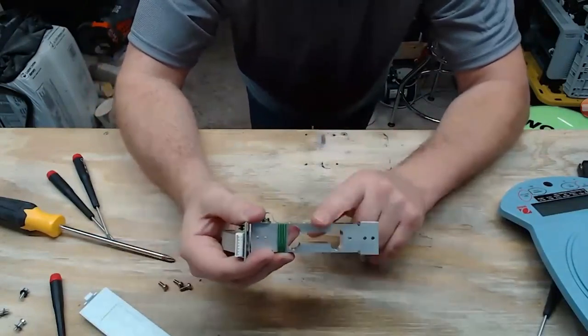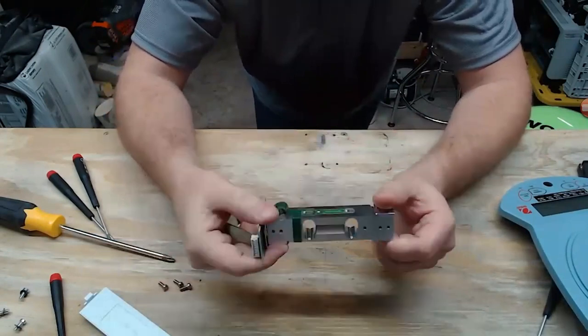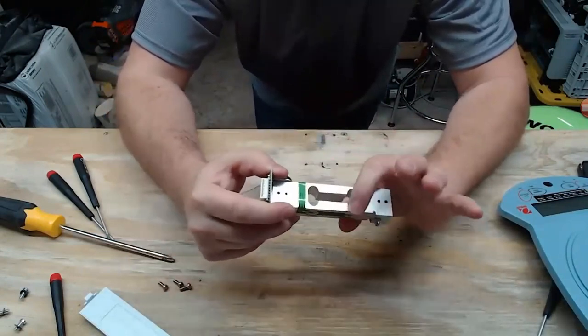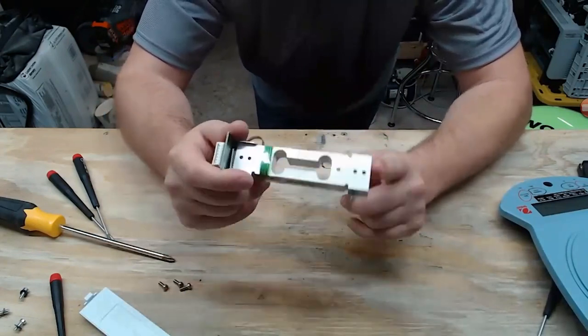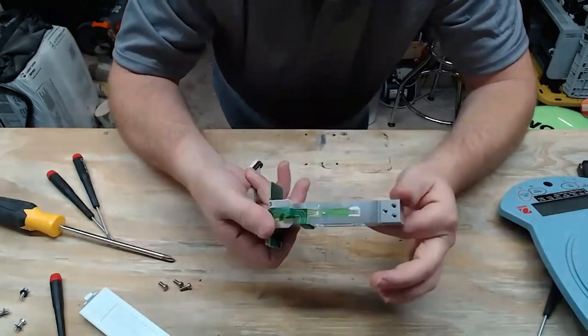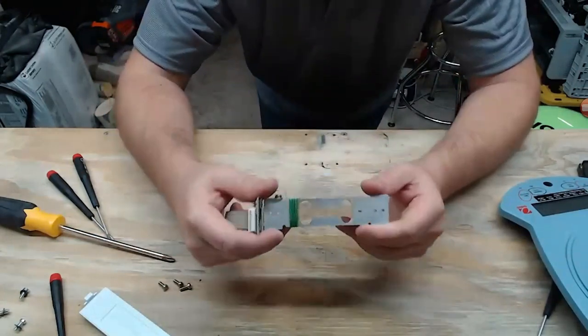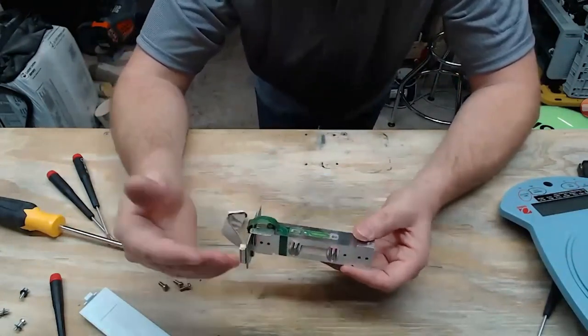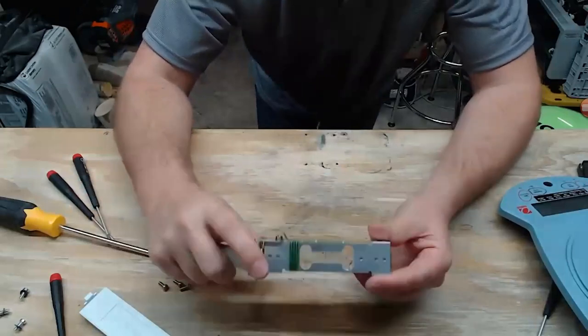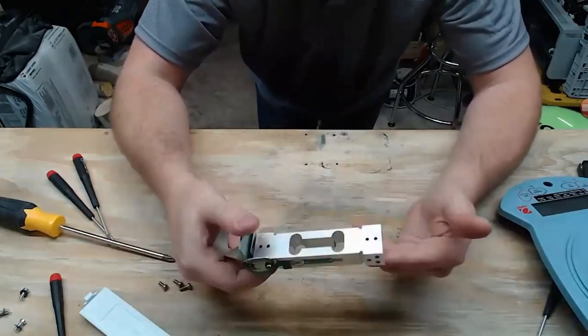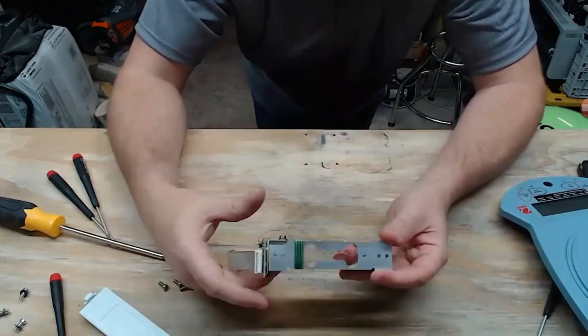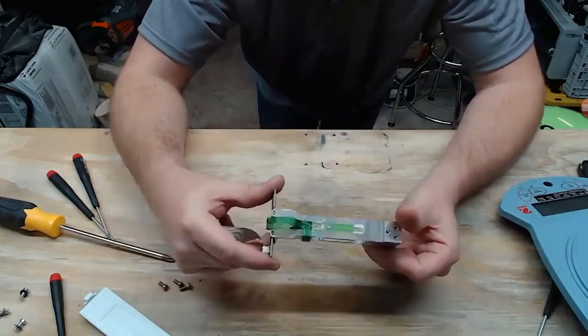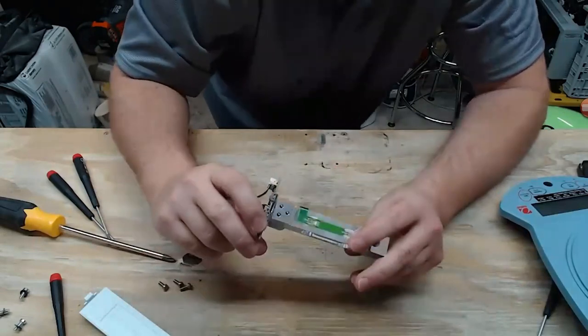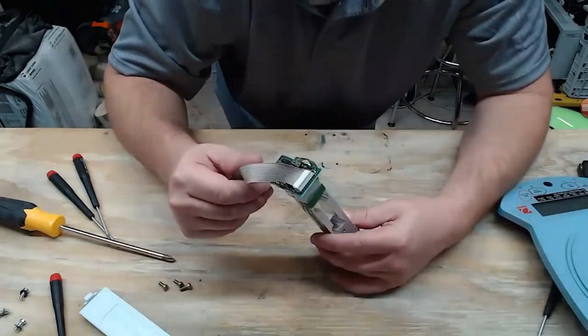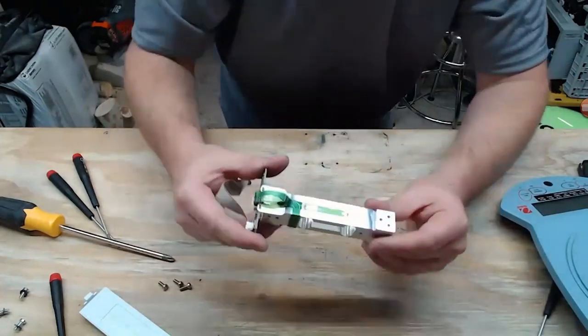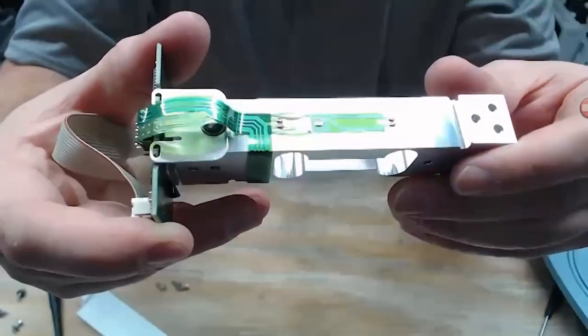That's actually really interesting. It's a sloppy way of doing it, but that's definitely a sure way, because what happens is as you add tension on one side and you get compression and you get expansion, that's going to change voltage measurements. These are going to be an analog signal, and they're going to come here to a board that's going to convert them to a digital signal, which is why I was referencing that they placed the board that's going to do the analog to digital conversion as close to your analog sensors as possible.